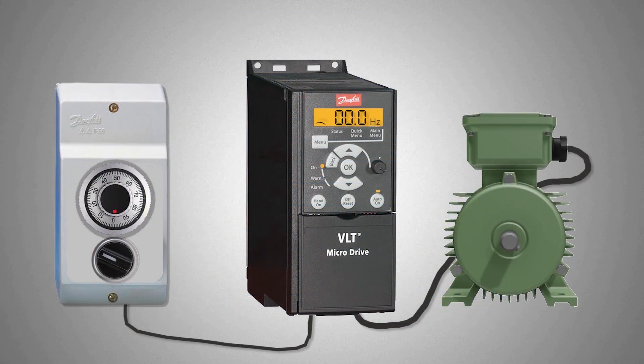After entering these parameters in the VFD we are ready to start the motor using a run command via selector switch and a potentiometer as a frequency reference source. Now if we turn on the selector switch the VFD goes into run mode but the motor is not running yet because the potentiometer is set to 0 and the analog reference signal is also 0.